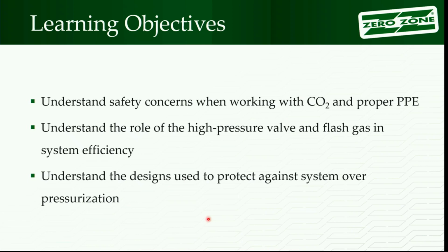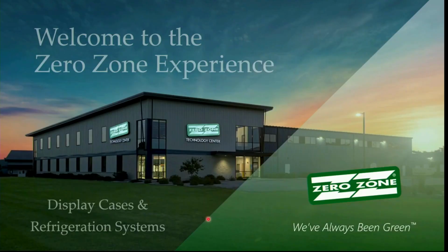Higher pressures, colder temperatures. Then we're going to spend time talking about that high pressure expansion valve and how that works with system efficiency. So you should be able to go home and know, I know why that valve's going up in pressure on a hot day. I know why that set point's moving. I know the reason why. Not what they told me it should go up, but I understand why, what it's doing with flash gas. And then lastly, some of the designs to protect the system from overpressurization. And that gets really into the service aspects you guys do.